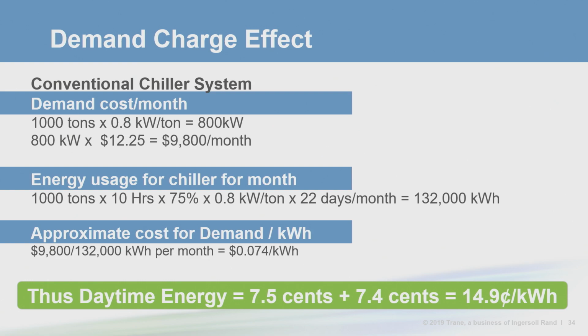So the denominator is the number of kWh that chiller plant consumes over the course of the month. It's a 1,000-ton unit operating, let's say, at 10 hours a day at a 75% diversity factor, multiplied by its efficiency, the 0.8 kW per ton, times 22 weekdays a month. That equals 132,000 kWh. When we take the $9,800 and divide it by the 132,000 kWh, we get an approximate demand cost of 7.4 cents per kWh.